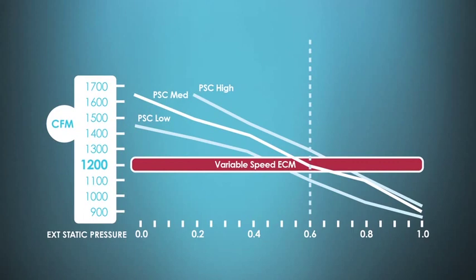However, I should point out — and you can see it on this chart — that we only guarantee that airflow up to around one inch of total external static pressure, because that's the way the manufacturer designs their system. So we will maintain airflow when external static pressure goes up, when filters get dirty, when registers are closed. However, there are even limitations to variable speed motors.